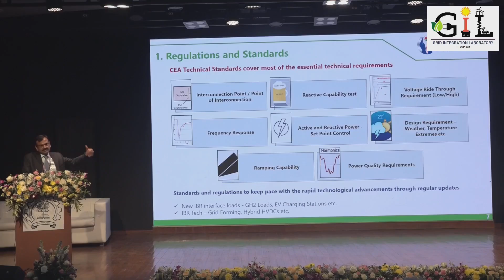Power quality is becoming more and more challenging when large IBR based resources are concentrated in a small area. At high voltage levels, there have traditionally been very few harmonics issues, as they get bypassed by our systems. But with these IBRs coming into one particular area, they all generate a lot of harmonics. With HVDCs, we have had filters acting as harmonics pass filters, but here too we need filters with different designs and approaches so that these harmonics do not disturb other plants. Otherwise, it can be catastrophic for some of the plants.